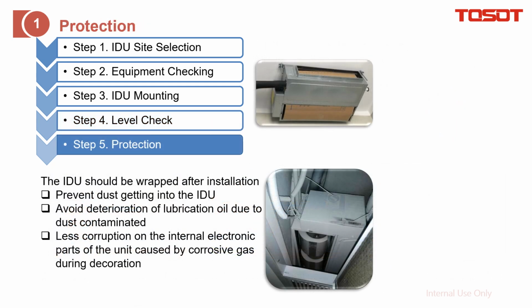And the last step is the protection. When we finish the indoor unit installation, you need to protect it. The reason is that after that, basically the indoor area is required to do the decoration, right? We're just afraid that during the decoration, the plating or the corrosive gas may damage this indoor unit. And here are the examples. First is this one. You can find it is just covered with cardboard, right?